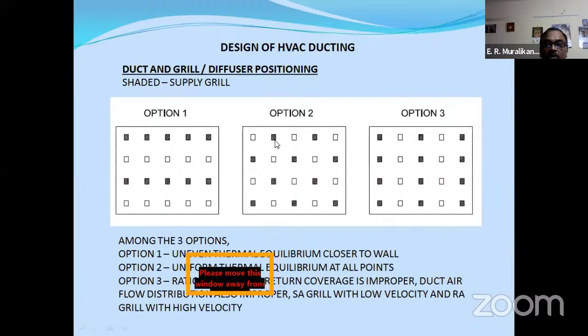Let us evaluate. Here the numbers of supply and return are identical. Here the supply is more and the return is less. Now what will happen is, if you don't have a proper return or duct sizing, the supply air velocity will be lesser than the return air velocity. So there will be whistling noise in the room. What generally people do is they put some FPM and size the duct. But in this distribution, the noise will be high, the return air pickup will be high, and thermal equilibrium will be poor. Whereas in this case, it will be much better because it is throwing air in crisscross directions everywhere.